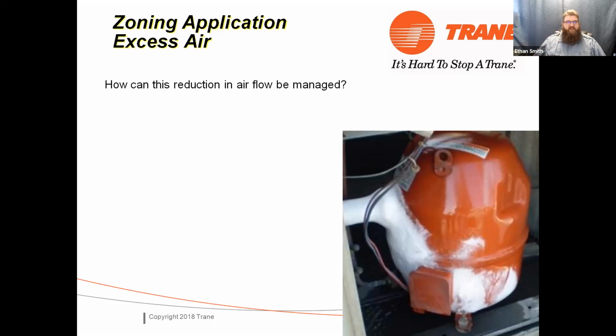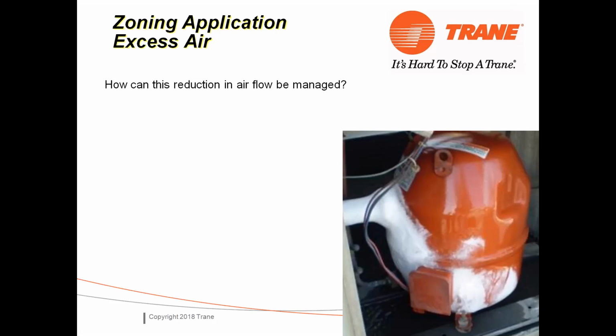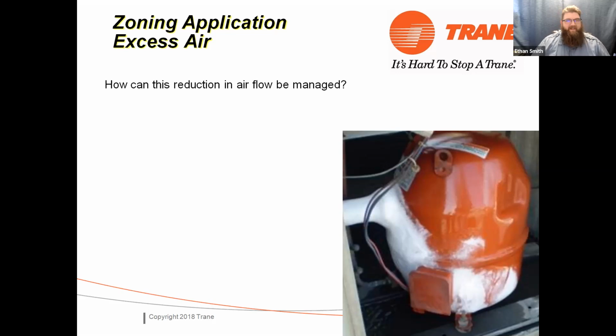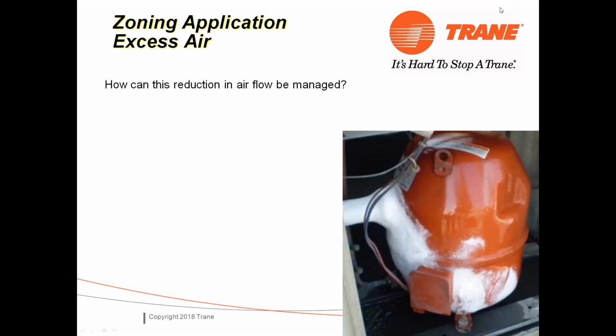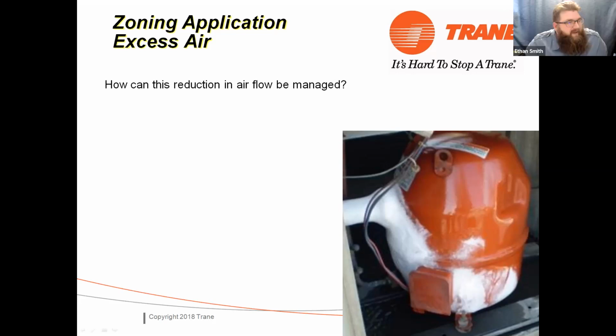What do you almost always see on a zoning system? It's usually down in the mechanical room. A relief. They have what they call a bypass. So some sort of bypass where the furnace or air handler will take air off of the supply duct before the dampers and simply pass it through to the return duct. Okay.